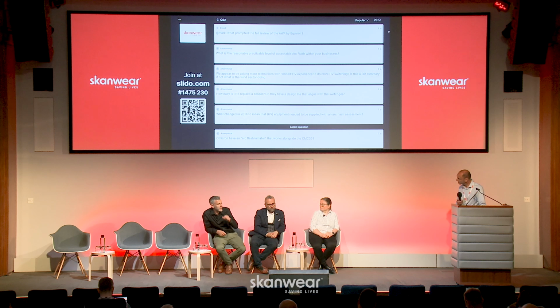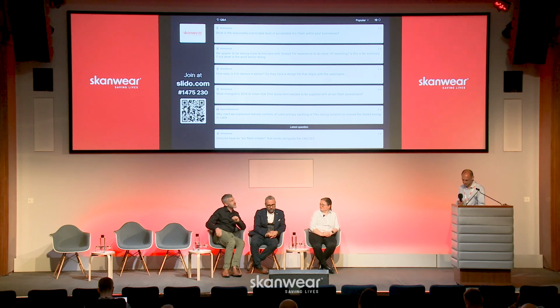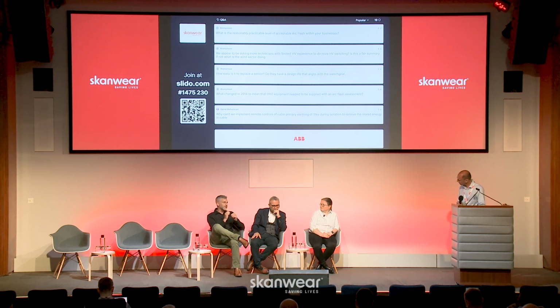No, there was no incident, it was just based on the arc flash calculations. There were obviously areas which were higher for the arc flash risk, so we wanted to make sure we were mitigating that. Are we doing the isolations in the right place? Are we putting people at harm? We suddenly knew we had this risk to manage - we always knew it, but now we had figures to put to it.